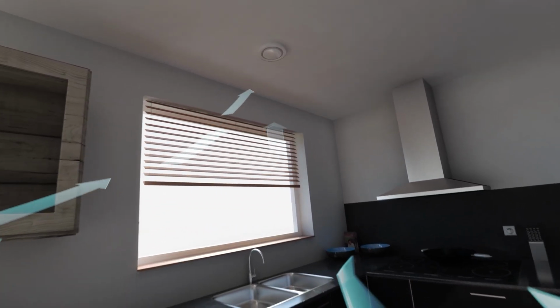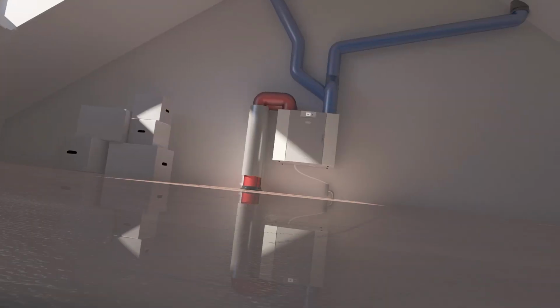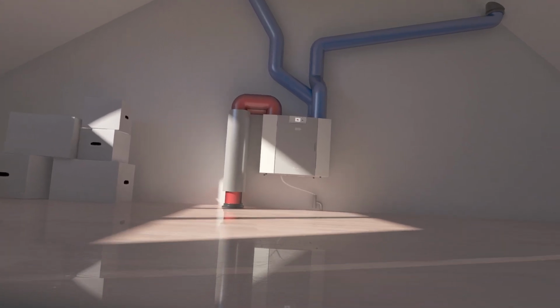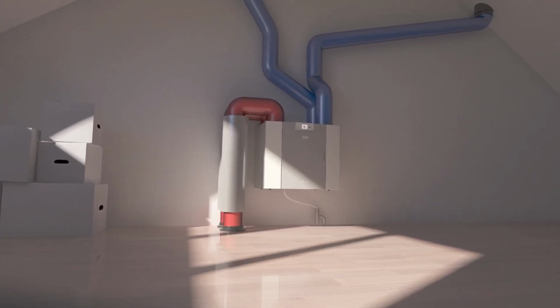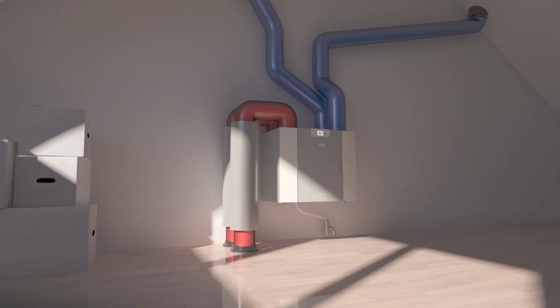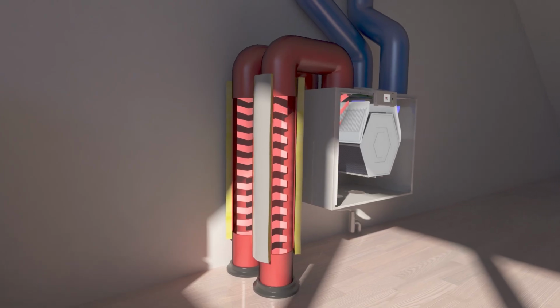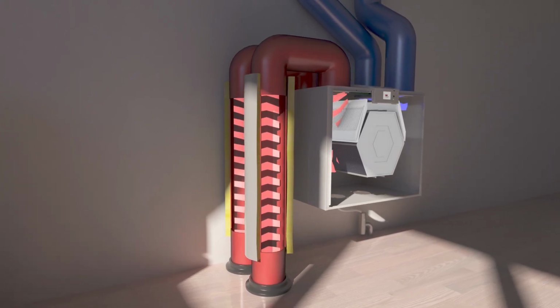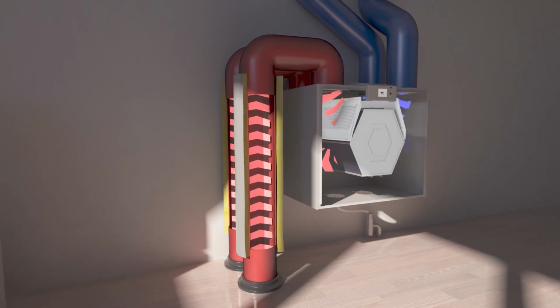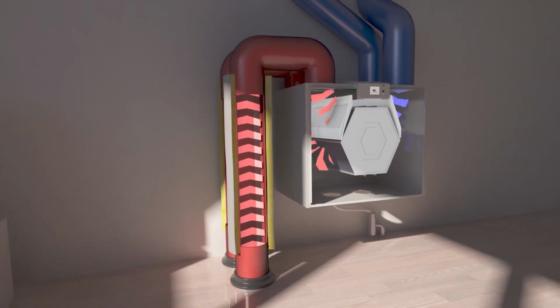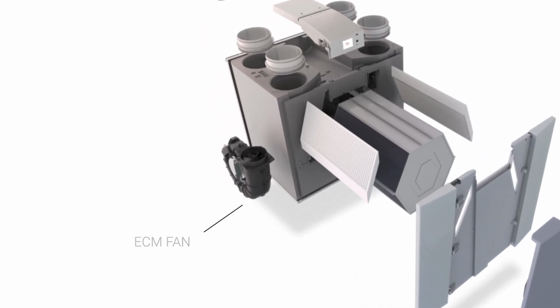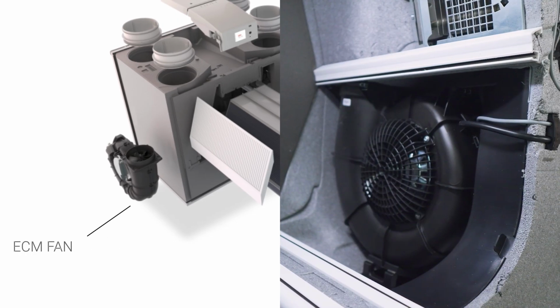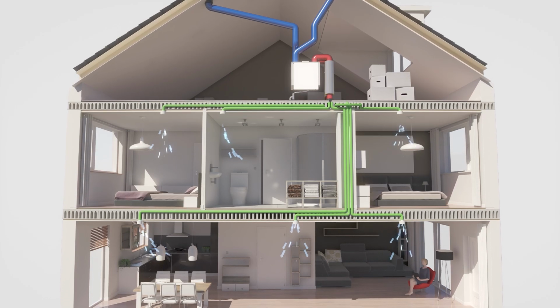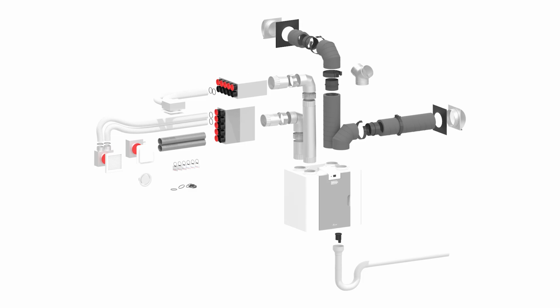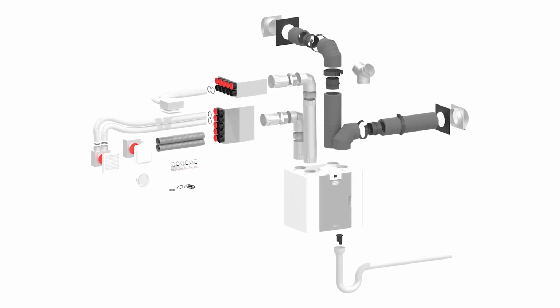Purchasing a high-performance, robust, and self-balancing Brink FLAIR unit and using a kitted system are the first two steps toward high-quality, balanced ventilation. The FLAIR unit has the latest technology for precisely balancing the supply and exhaust airflows with vane anemometers. The unit's ECM fans respond to pressure in the system or ductwork. Using a kitted home-run distribution system helps reduce installer errors.